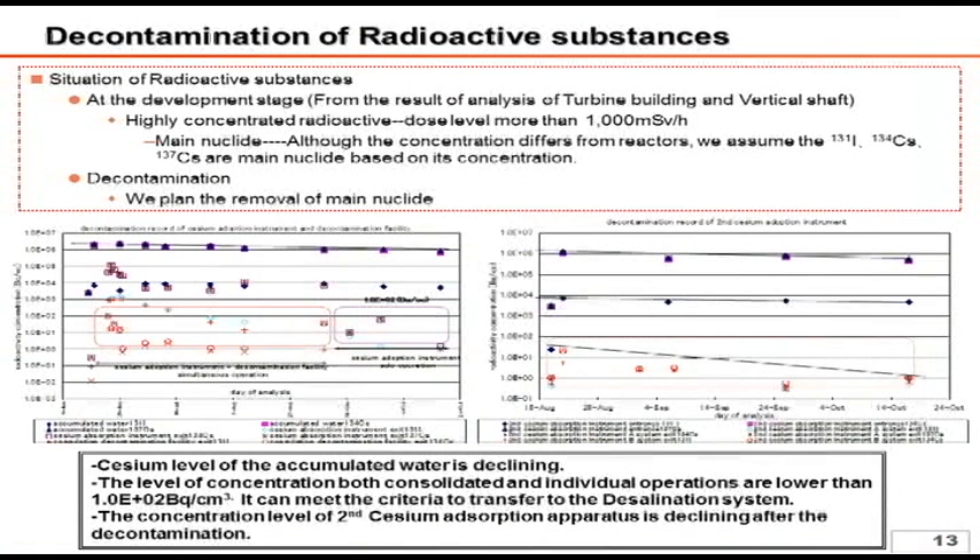Next, I will address the track record of the water treatment. We expect that the system is capable of reducing the dose value of high-level radioactive water from 10 to the 6th power becquerels per cubic centimeter to 10 to the 0th power or 10 to the 1st power becquerels per cubic centimeter.